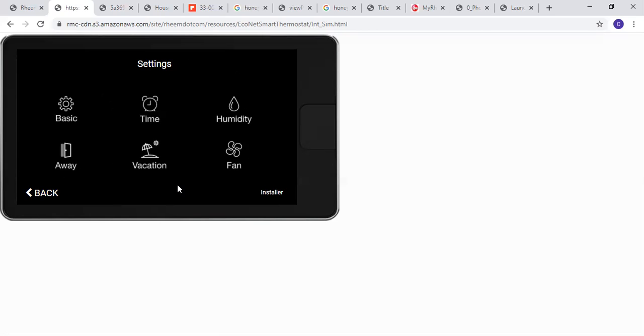Also, if you're using the EcoNet and you have a communicating outdoor unit, you'll also have the option to go into test mode here as well to test your outdoor unit. If it's a two-stage AC, you can pick first stage, second stage. If it's an inverter, you can pick low, medium, or high. Or the newest one says charge heat, charge cool. So that's going to be your highest setting.